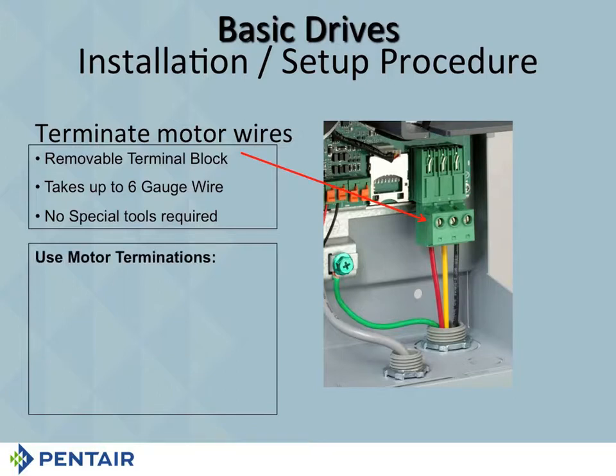If you're using a 3-phase motor, our 3-phase motors have red, black, and yellow as their wire colors. And I'm going to tell you, when I first saw that, I just kind of had a cow, because I was a little upset about that. I thought, why are you using single-phase colors? How is anybody supposed to know if you've got a single-phase or a 3-phase motor down there? And then I came to my senses and realized all you got to do is put an ohm meter on there and ohm it out. If red and yellow are the same as black and yellow, you got a 3-phase motor, because normally red and yellow would be higher than black and yellow. That's all you have to do, all right? If you hook them up the way they're color-coded, you'll never have to worry about this motor running backwards. It will always run in the correct direction, and that's why they did it that way, all right?